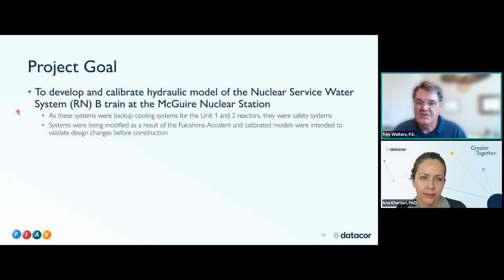The project goal was to develop and calibrate a hydraulic model of the nuclear service water system B train at the McGuire Nuclear Station. These systems were backup cooling systems for the Unit 1 and 2 reactors. And so they weren't the primary cooling system, but if the primary cooling system had issues, then they would draw on this RN service water system to provide cooling water to the reactors. So these were considered safety systems. And those of you in the nuclear industry know that this whole project had to be done with nuclear certified safety, as a nuclear certified type of project.